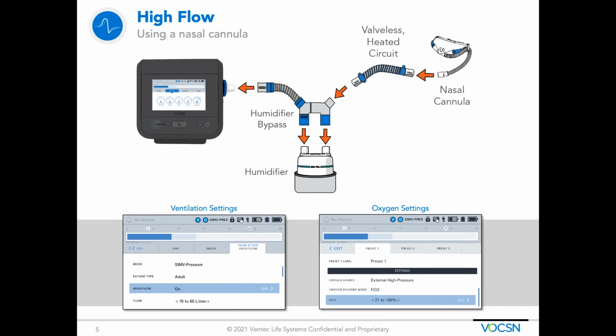But the V+ Pro and the V+ that's an emergency vent are just ventilators. They don't have the oxygen concentrator in them, which makes them simpler. So I asked the guys, Samir Ahmad, who I think might be on, put these figures together. The device was intended to be able to do high flow nasal oxygen if you wanted to, and this just shows the screens. You pick the ventilation settings and select high flow is on, and you select oxygen settings and set the FiO2.